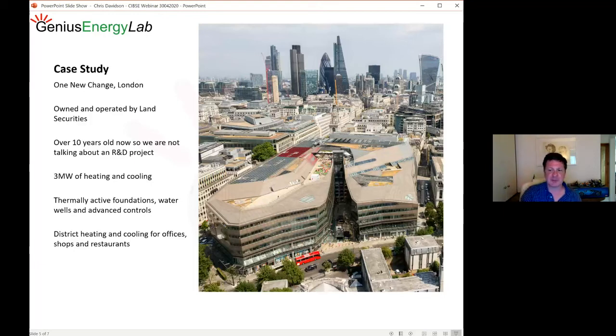That's the view down on the building from the dome of St Paul's Cathedral, if you want to get your bearings. It's about 3 megawatts of heating and 3 megawatts of cooling. There are thermally active foundations, closed loops in the foundations of the building, coupled with water wells taking water from the chalk at about 80 meters down, using that water to either reject or extract heat from the ground and then putting it back into the ground again.